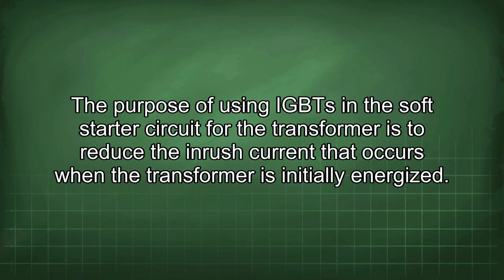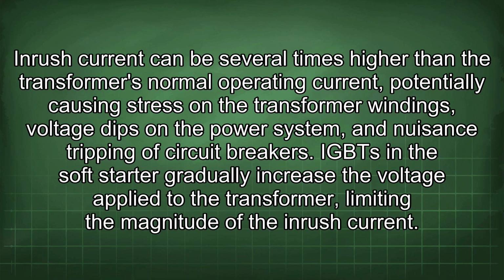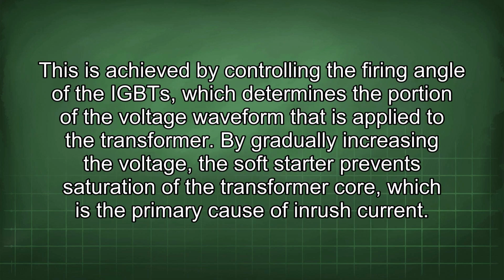event. The purpose of using IGBTs in the soft starter circuit for the transformer is to reduce the inrush current that occurs when the transformer is initially energized. Inrush current can be several times higher than the transformer's normal operating current, potentially causing stress in the transformer windings, voltage dips in the power system, and nuisance tripping of circuit breakers. IGBTs in the soft starter gradually increase the voltage applied to the transformer, limiting the magnitude of the inrush current. This is achieved by controlling the firing angle of the IGBTs, which determines the portion of the voltage waveform that is applied to the transformer.